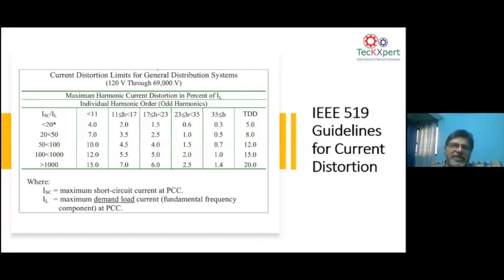Because any capacitor, when it works with an inductance, naturally the network will have a natural frequency. And if that natural frequency becomes closer to a harmonic frequency like 3, 5, 7, 11, then naturally that network can create resonance. It can be either a parallel resonance or a series resonance. A parallel resonance can happen inside a facility itself because your capacitor, your harmonic load, your transformer, everything is in one place. But in a series resonance, you can have harmonics flowing from elsewhere and maybe disturbing or destroying your plant.